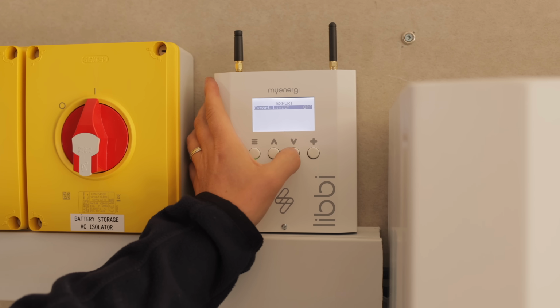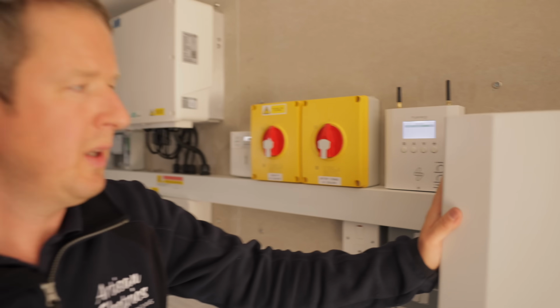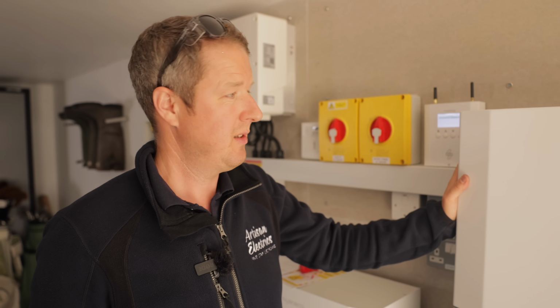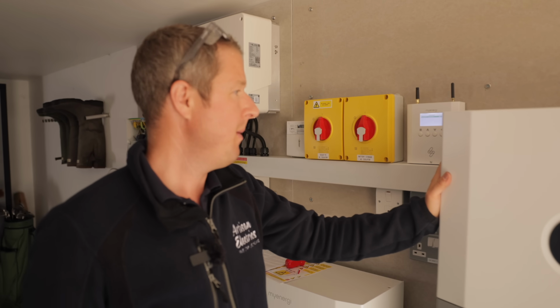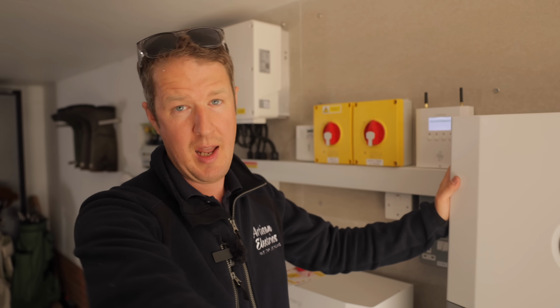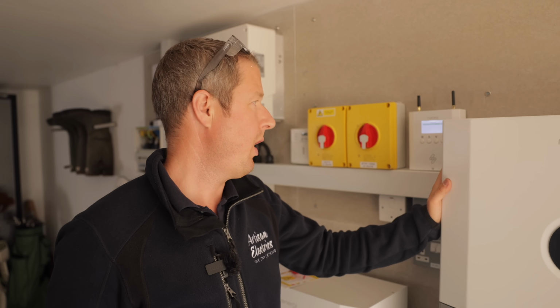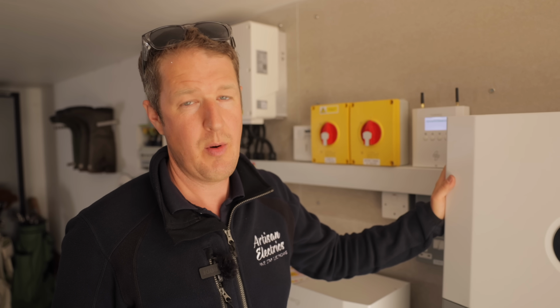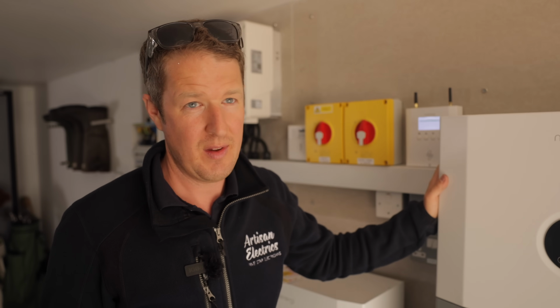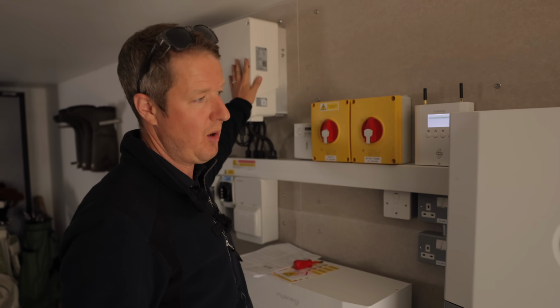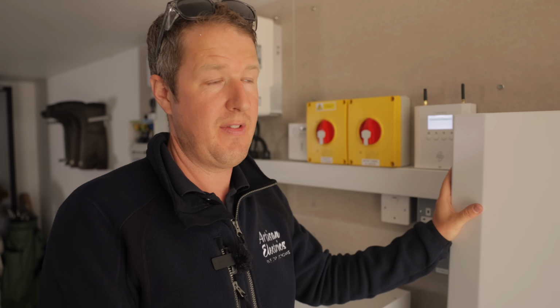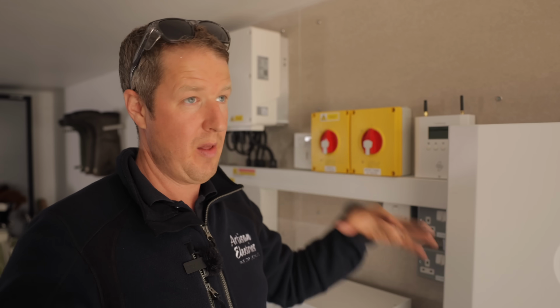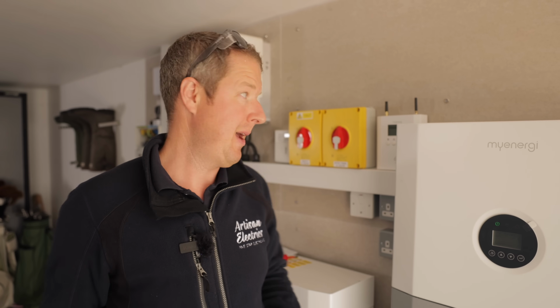The other thing is an export limit. Now, you have to get G99 approval to install a 5 kilowatt inverter to the grid, even if it's just a battery inverter, because technically you could force discharge the battery and export 5 kilowatts out to the grid. So some DNOs, or distribution network operators, will require an export limit to be set on the site. For example, here we've got an 8 kilowatt solar inverter, we've got a 5 kilowatt hybrid inverter for the battery here, we've got another 3.6 kilowatt inverter in the house as well. So total potential export at this site is like 16 kilowatts. But the DNO have not mandated an export limit. However, sometimes they might do.